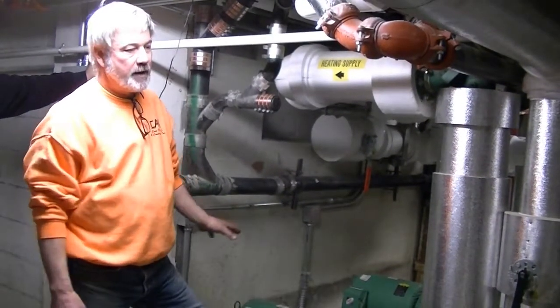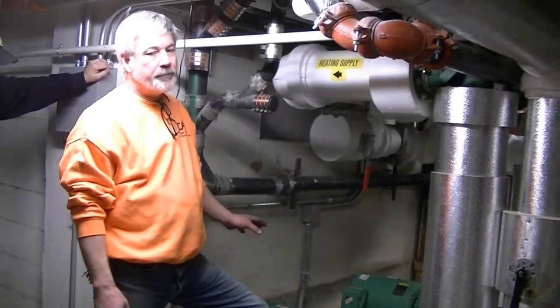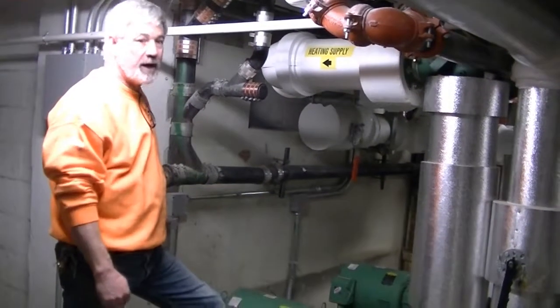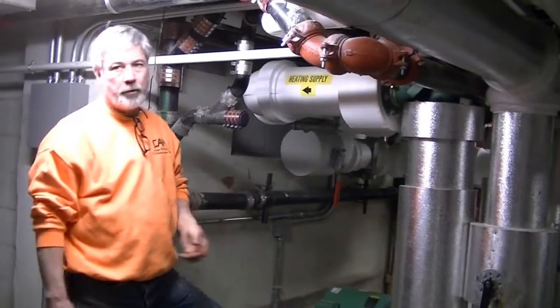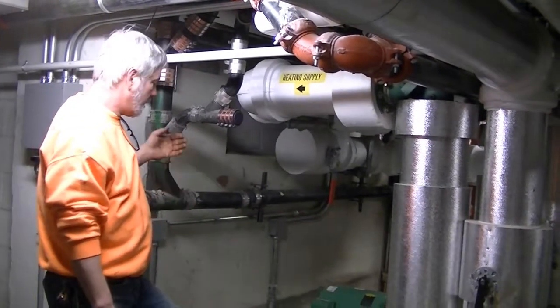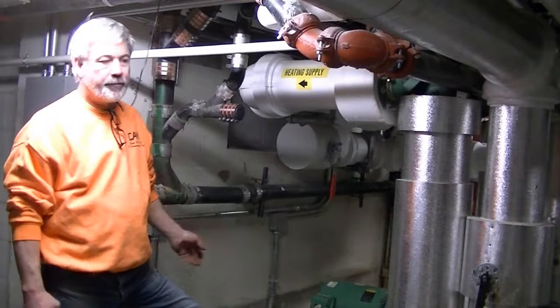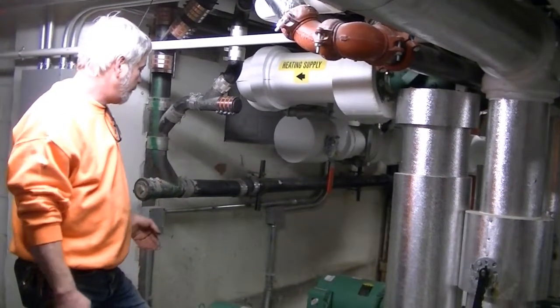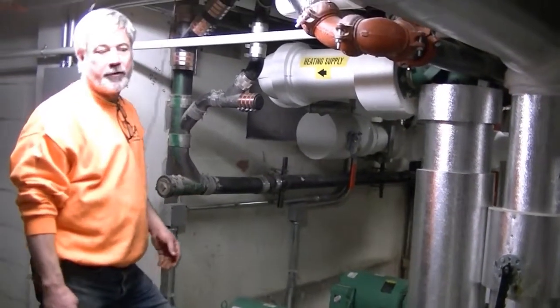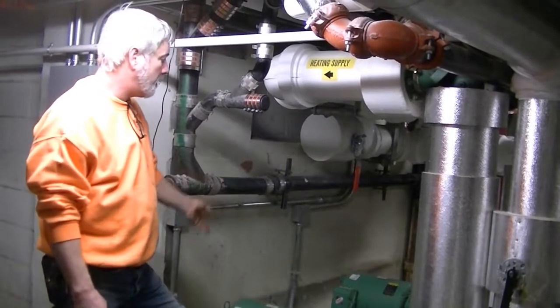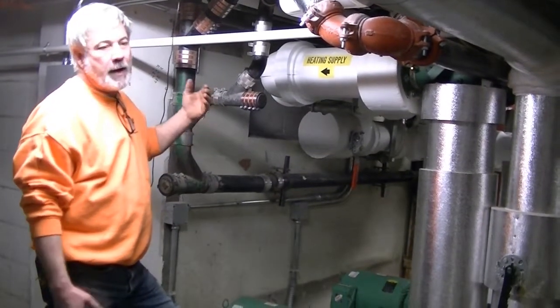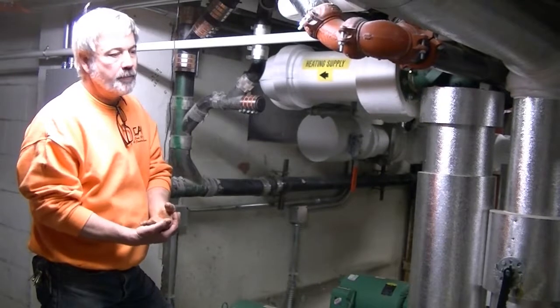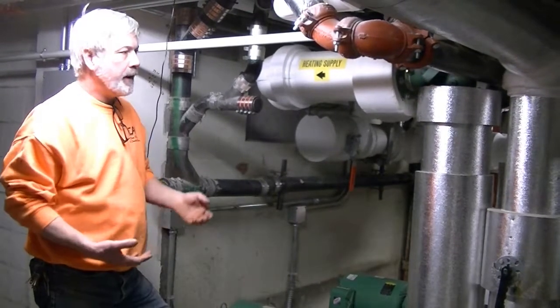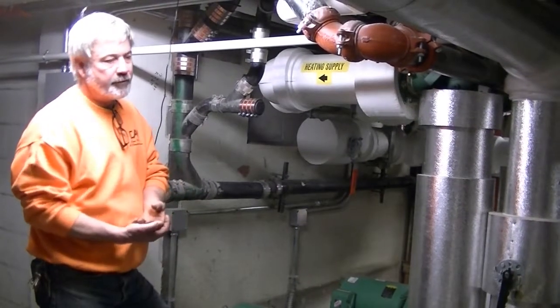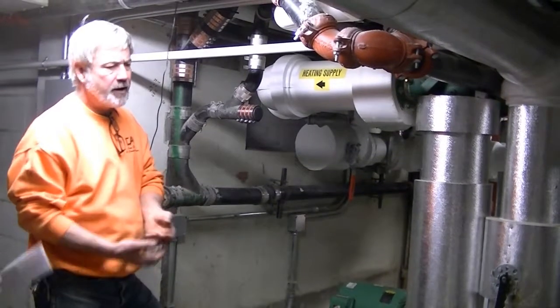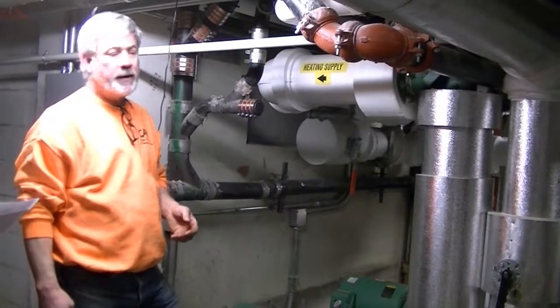Every 6. I mean, in the wintertime, there's going to be obvious telltale signs that you've got a problem. You hear the motor making noise. You'll get some vibration, things like that. Running hours is another thing that you would have to look at. These pumps come on when the outside air temperature drops below a certain set point. And I believe it's 65 or 70 degrees, and then the pumps come on. Okay. Basically once a year.